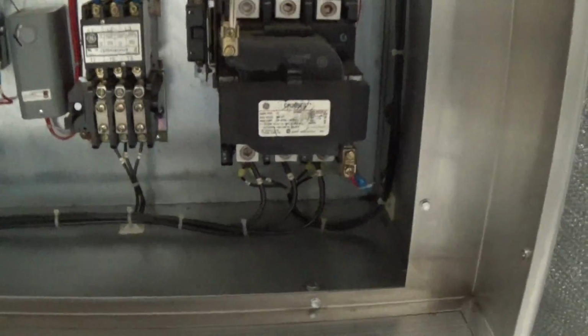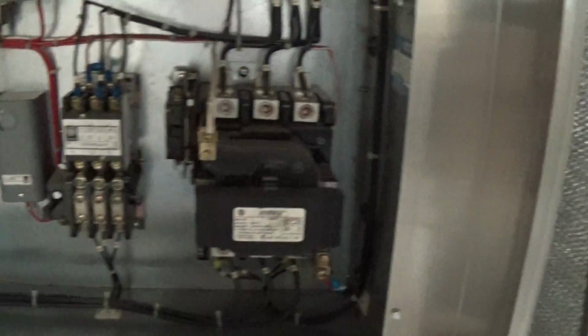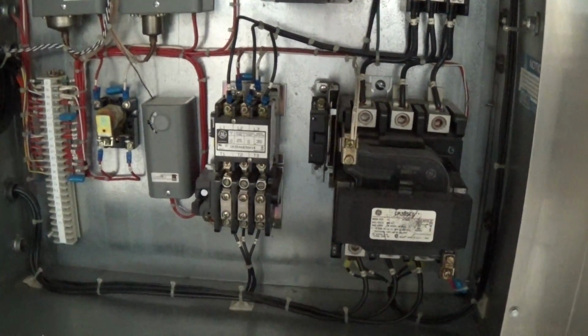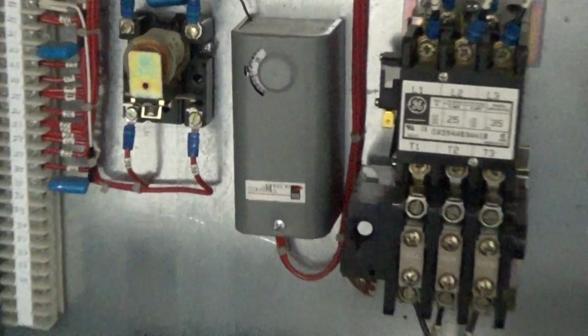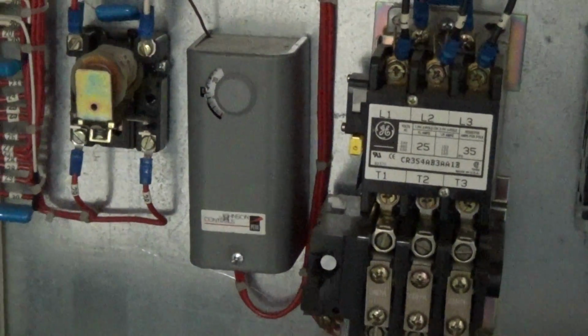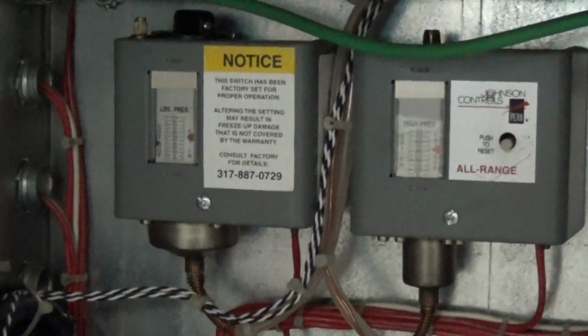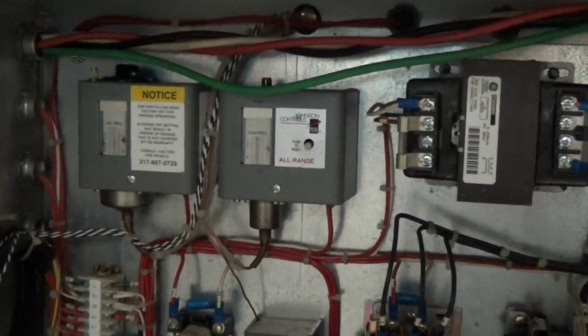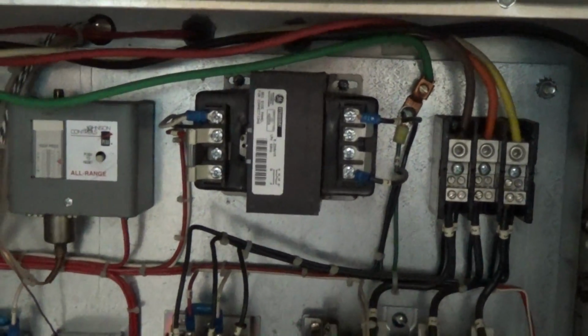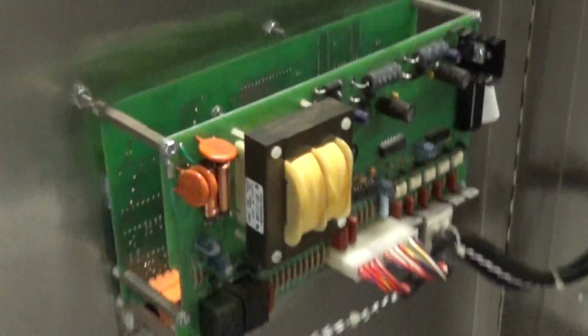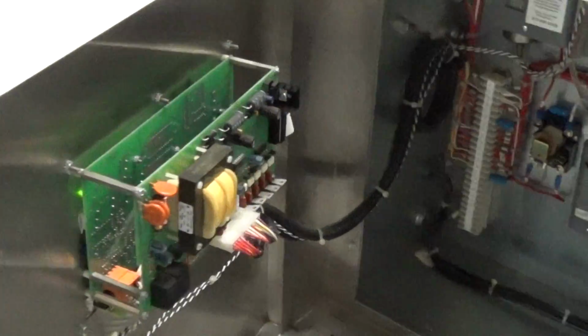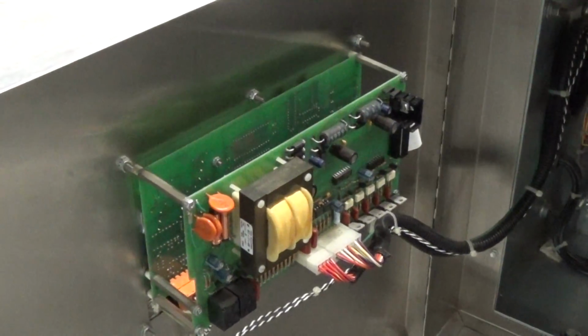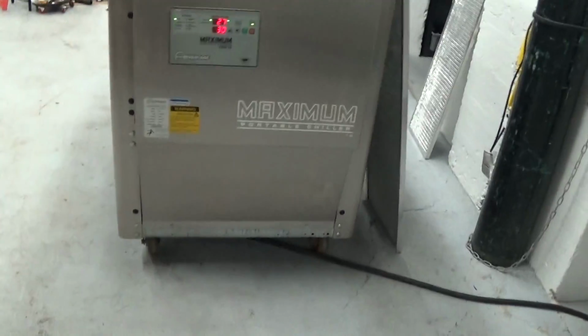Our fan power comes right off the main contactor here. This contactor and overload is for the pump. That's your freeze stat, which will be adjusted accordingly for brewery applications. And that's your low pressure cutout and high pressure cutout. You shouldn't have to adjust that. If you have any questions, call us. And the nice Advantage / Temp Tech controller. They have their own controls subdivision of their company there now too, which is nice. And this unit was made in Indiana, and that's where it's shipping, which is great.